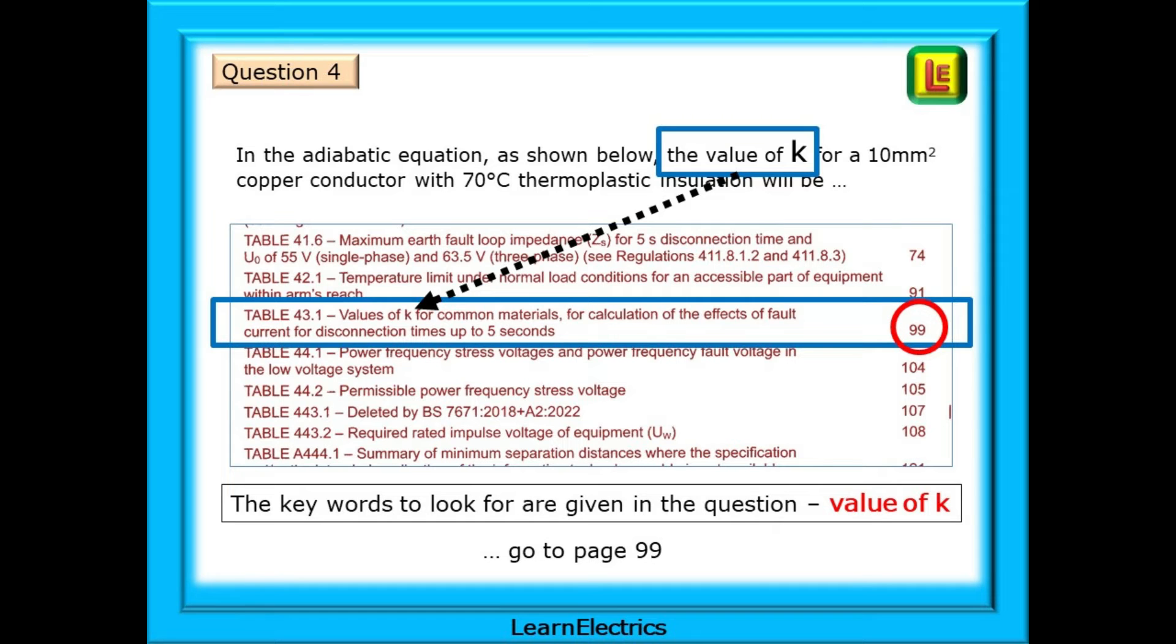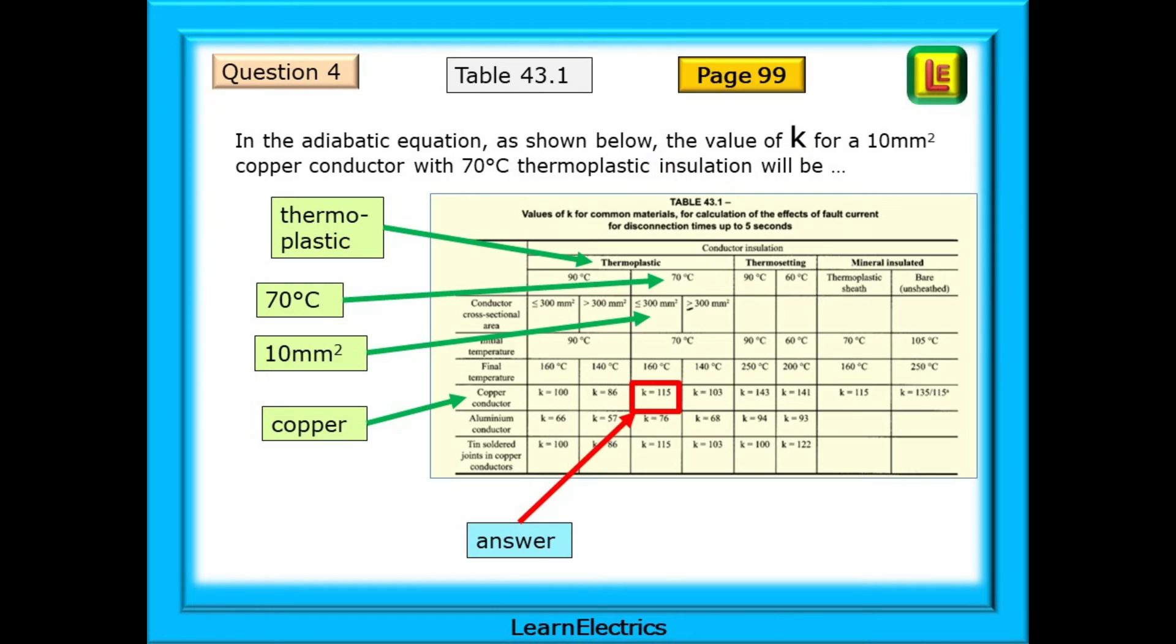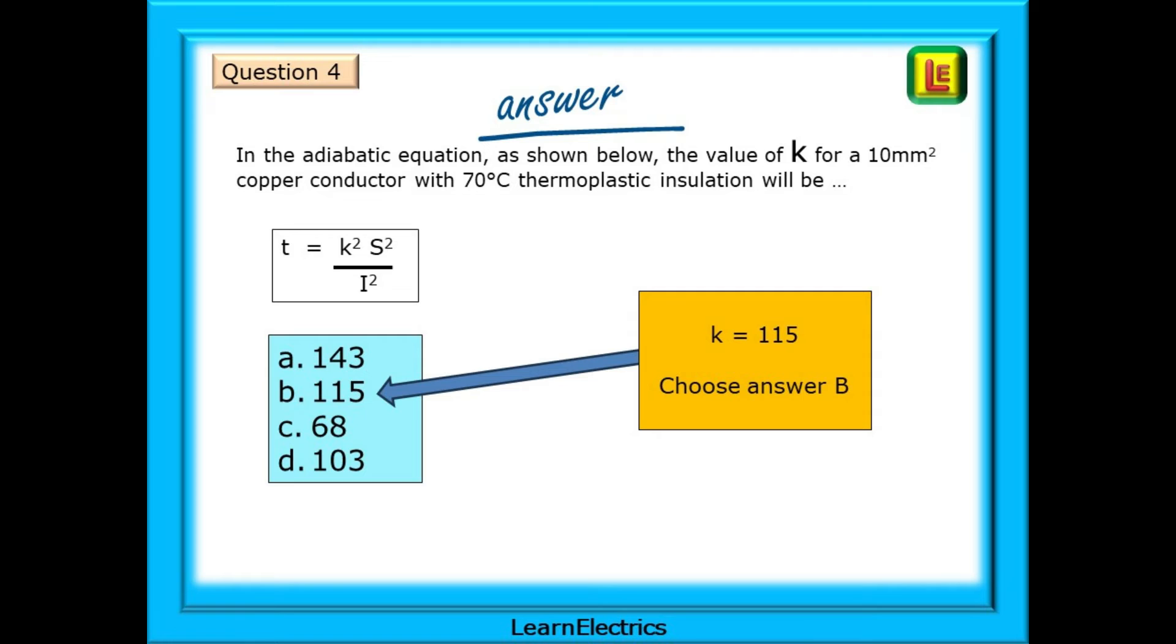The key words to look for are values of K, and table of tables shows that this is on page 99. Just as before, use the information in the question to narrow your search down to columns and rows. Thermoplastics is first, and this eliminates half of the table. Now, 70 degrees, and we are down to just a quarter of the table. The question tells us 10 square millimetre conductors. So, find the column that shows up to, but not more than, 300 square millimetres. And there is only one column of interest now. Look down the left-hand side, and find the word copper as given in the question. Where row and column cross is our answer. K equals 115. Now that we know that K is 115, we should choose answer B. And how easy is that?